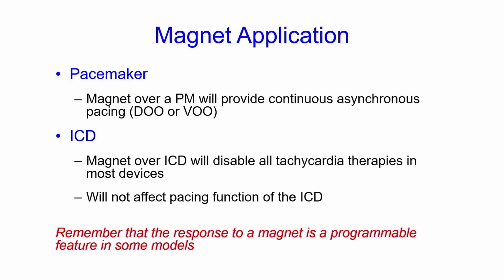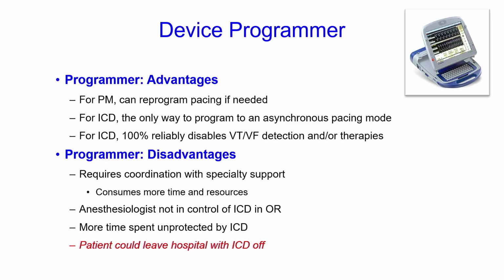but it has no effect on pacing. What I put down in red at the bottom of the slide is remember that the response to a magnet can be a programmable feature in some devices. So some devices may not respond to the magnet because it's programmed not to until you turn that feature on. So you want to make sure that you're aware of that before going to the OR and just placing a magnet on, and make sure that it's not in a mode where it won't respond to the magnet.